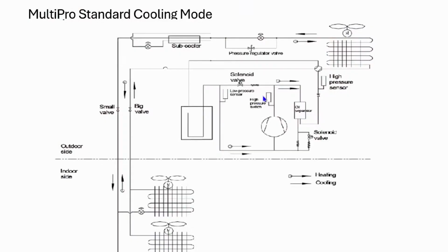Right. You do have high pressure switches in it, as you can see in this diagram, but that doesn't mean the machine's going to fault on high pressure before it faults on something else. It also depends on the type of restriction, and I've dealt with this even with standard equipment. When you have a block in the refrigerant, let's say your restriction, maybe we close this service valve back and we start backing that liquid up in here. This is what I've seen even in traditional equipment.